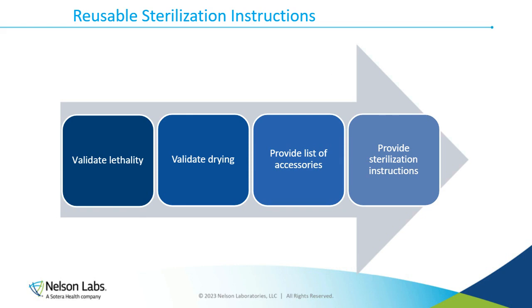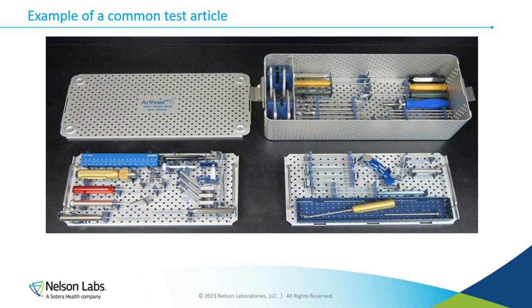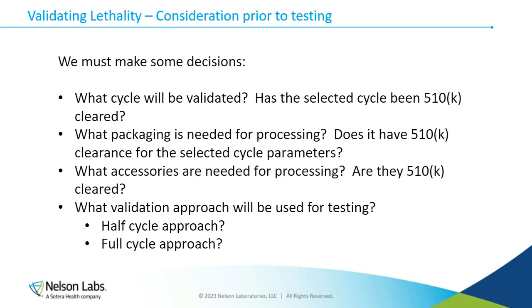The first step of the process is to validate the lethality. The process flow is: select inoculation locations for the test article, inoculate that product, package it, expose the product to our validation conditions, perform a sterility test on those biological indicators, and then score them for growth. Here is an example of a common test article we might see when performing a validation for a reusable device customer, though we do see quite a variety.